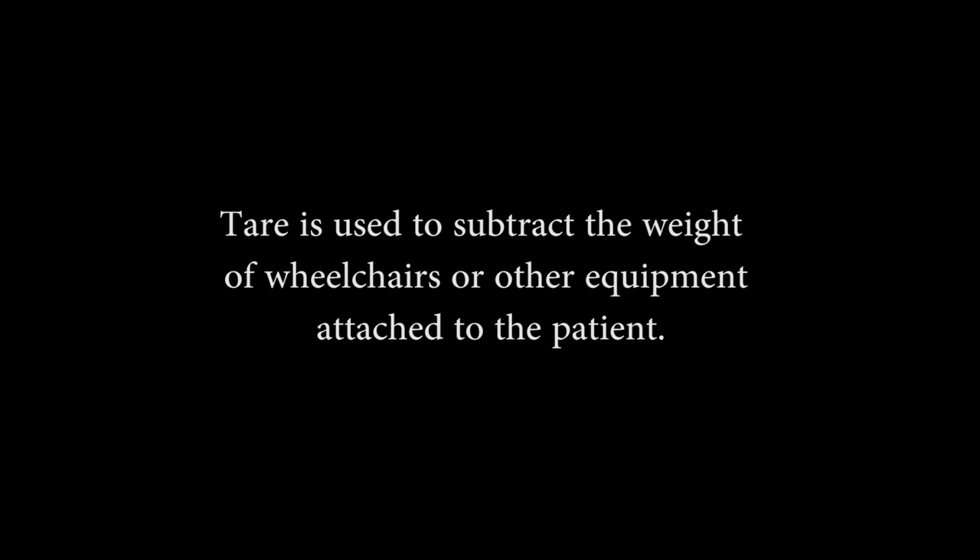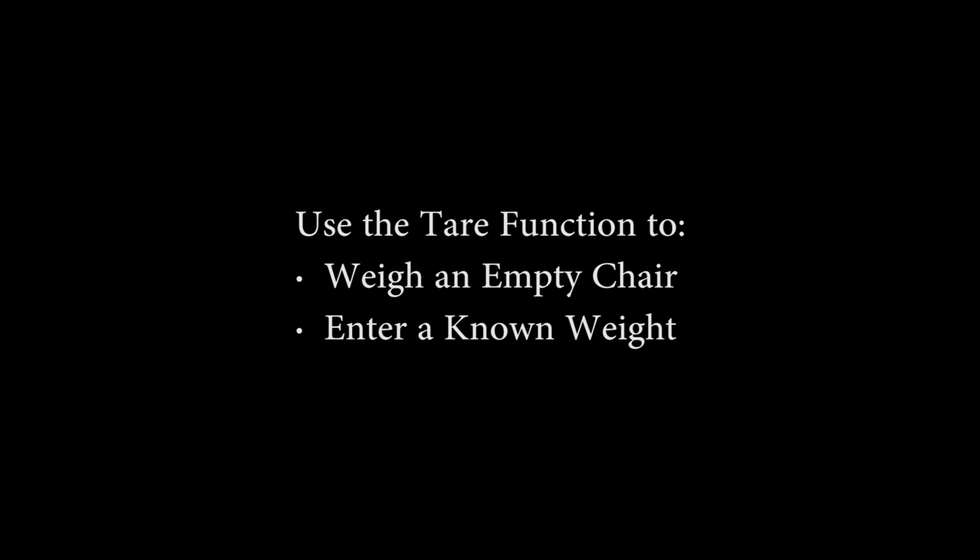Tare is used to subtract the weight of wheelchairs or other equipment attached to the patient. You can use the tare function in one of two ways: by weighing an empty chair, or by entering a known tare weight value.